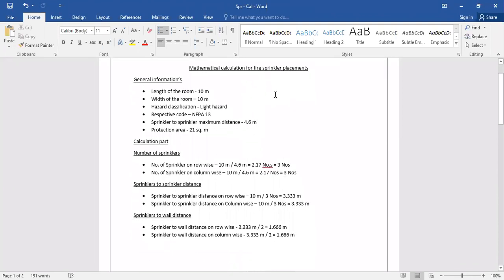First, I have listed out the general information: length of the room and width of the room, both are 10 meters, as found from the architectural drawing. The hazard classification and design criteria are based on NFPA 13. I assume this room as light hazard, and as per NFPA 13, the sprinkler-to-sprinkler maximum distance is 4.6 meters and the protection area is 21 square meters. These limitations are from NFPA 13.